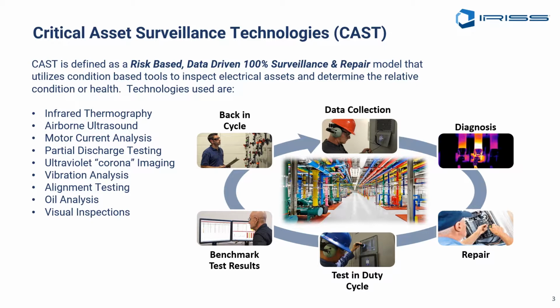The technologies involved are infrared, ultrasound, that can be airborne ultrasound or contact ultrasound. We can use motor current diagnostic tools, motor current analysis, motor current signature analysis, partial discharge testing, which is a little bit different than ultrasound. Can be involved in medium and high voltage equipment where we're actually trying to detect defects inside insulating materials of the equipment. We can use ultraviolet imaging cameras that will detect corona, primarily used in utility applications, but something that's useful nonetheless. Vibration analysis on a lot of equipment can detect problems. Contact ultrasound can be used in conjunction with vibration analysis on both mechanical and electromechanical assets. Alignment testing, oil analysis on transformers, of course, and then visual inspections.